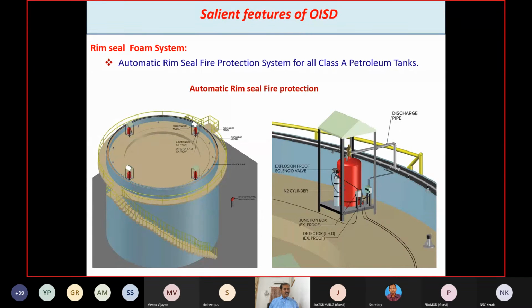Actually, rim seal fires occur in the edge region of the rim seal of floating roofs. If the seal is damaged, the vapor inside the tank comes out and mixes with the air, and it can get ignited during lightning. So a rim seal fire protection system should be provided, and the modular foam tanks will be located at the top at equal distances, and the linear heat detection tube senses the heat. Within 10 seconds it will operate, and the modular foam is pressurized with nitrogen gas, so it will release the foam, and the entire rim fire will be extinguished instantly.